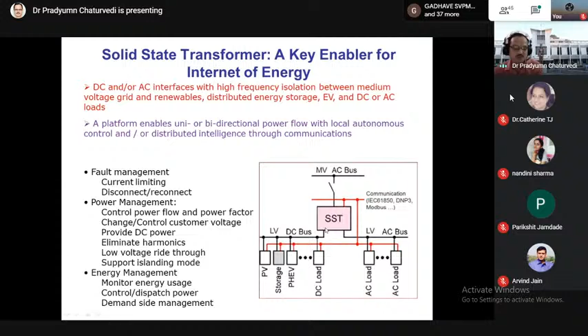The main advantage of SST over traditional transformer is high power density, because we are using one high frequency transformer for isolation, so the overall size of the system will be reduced, around 1/10 of the size, giving high power density.